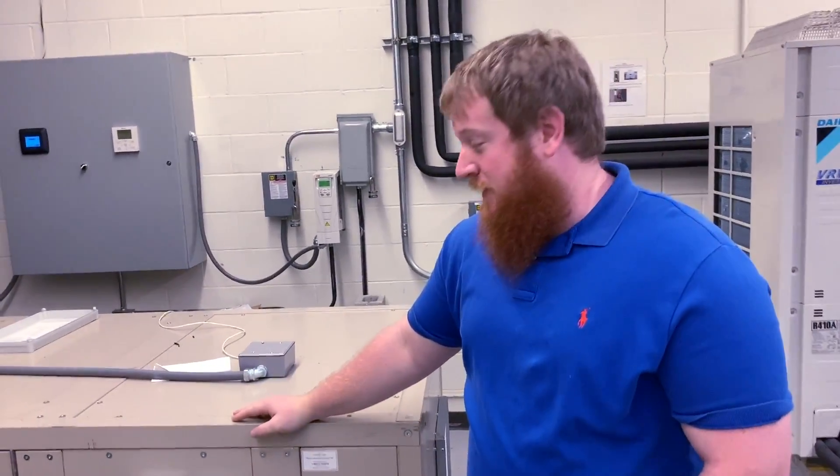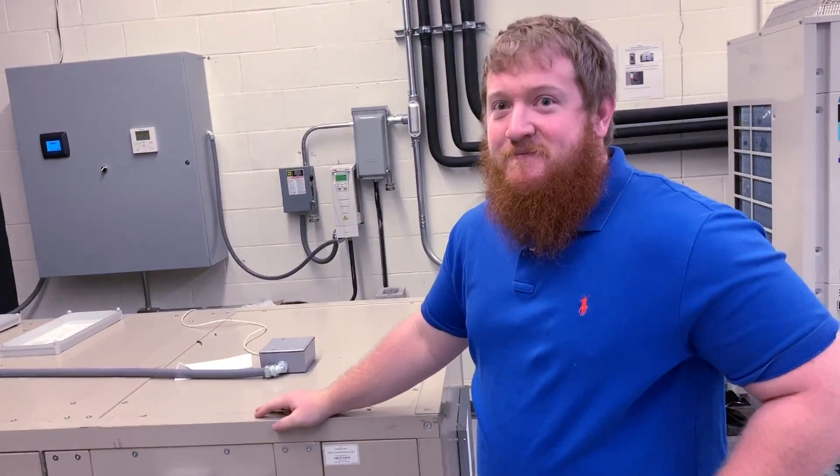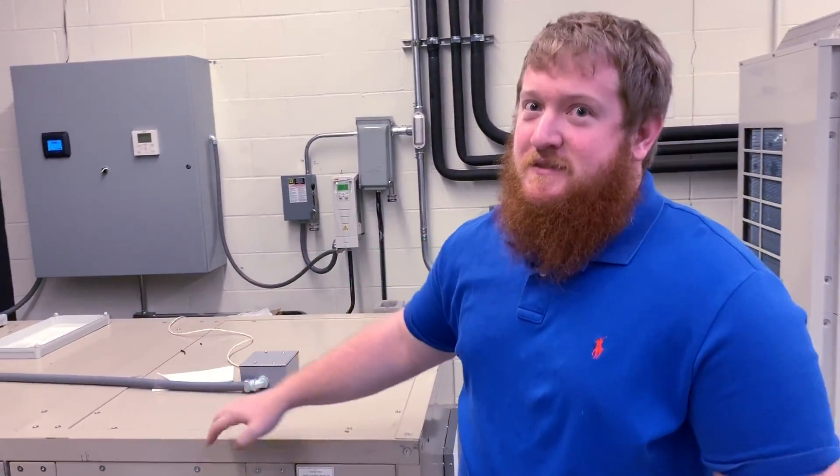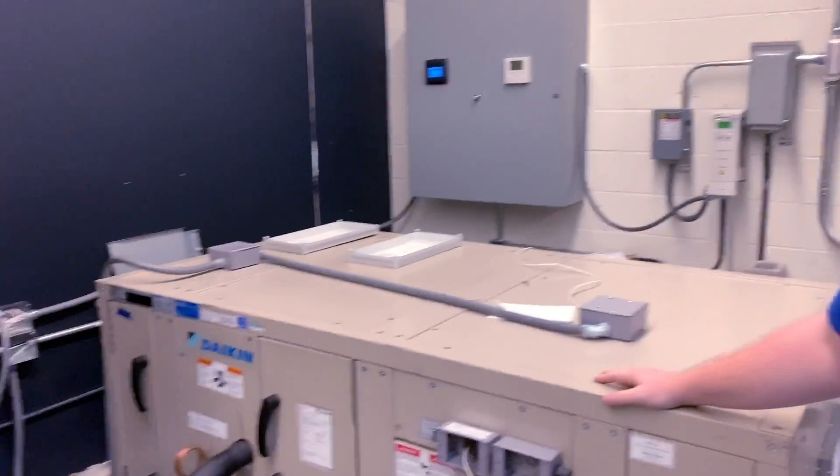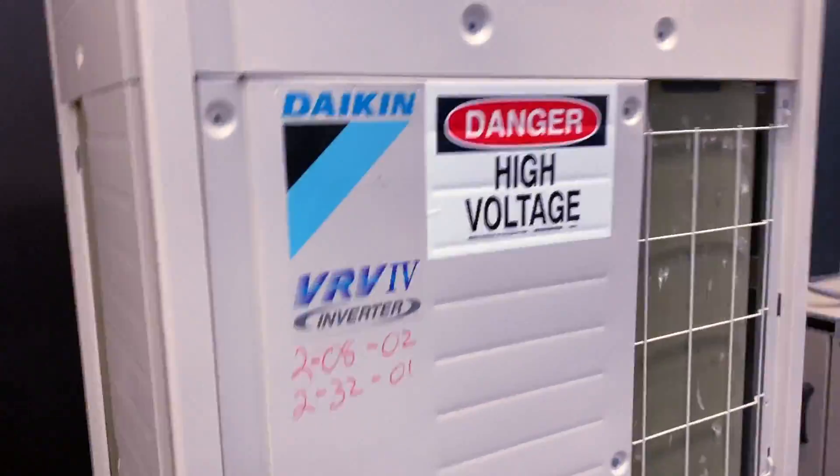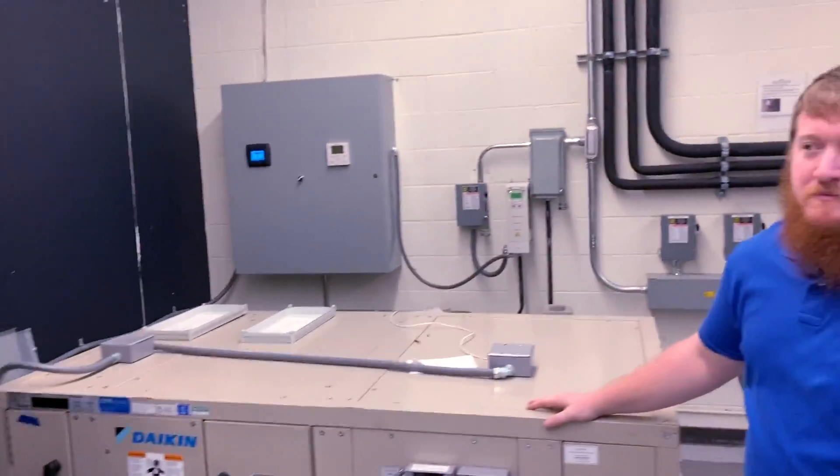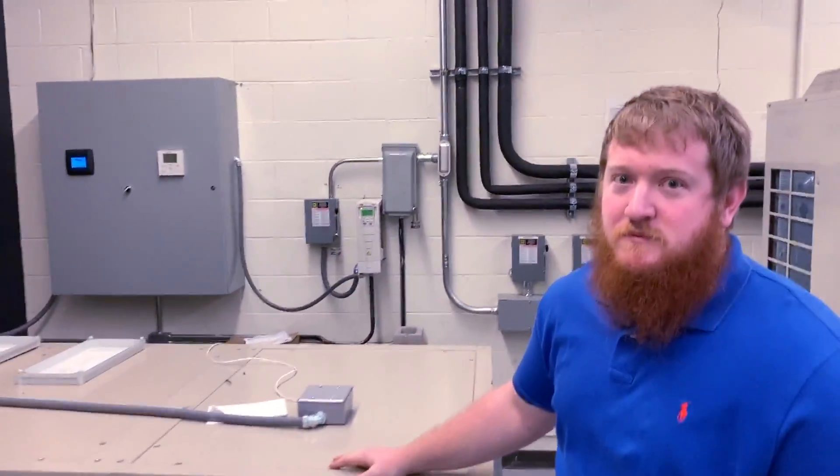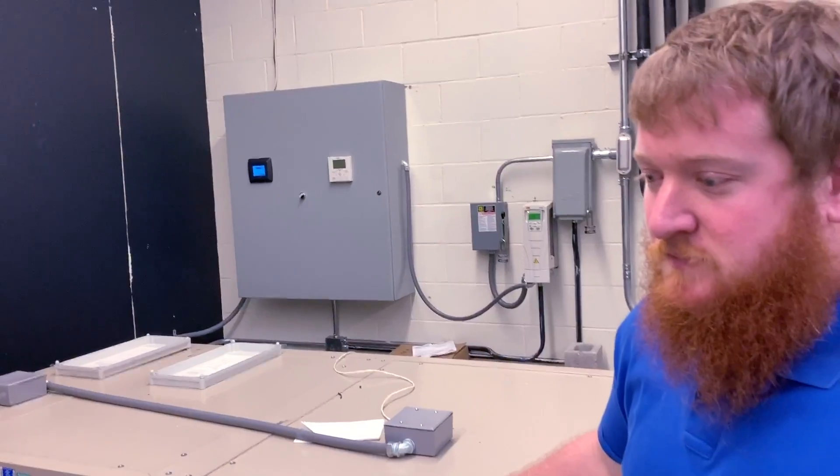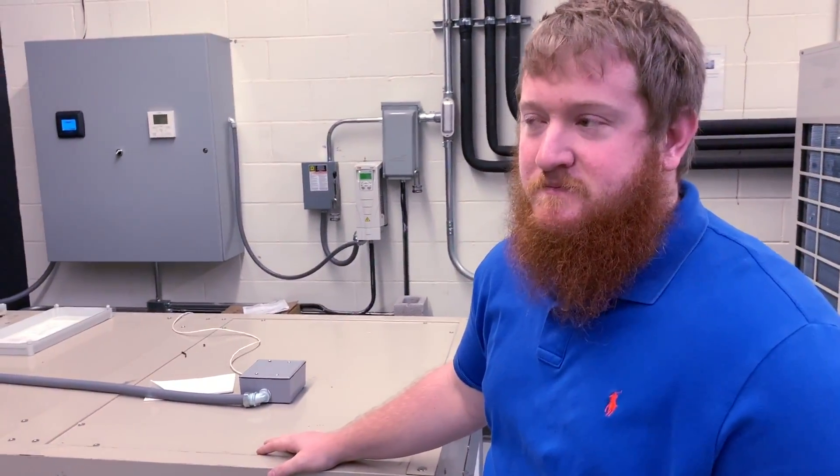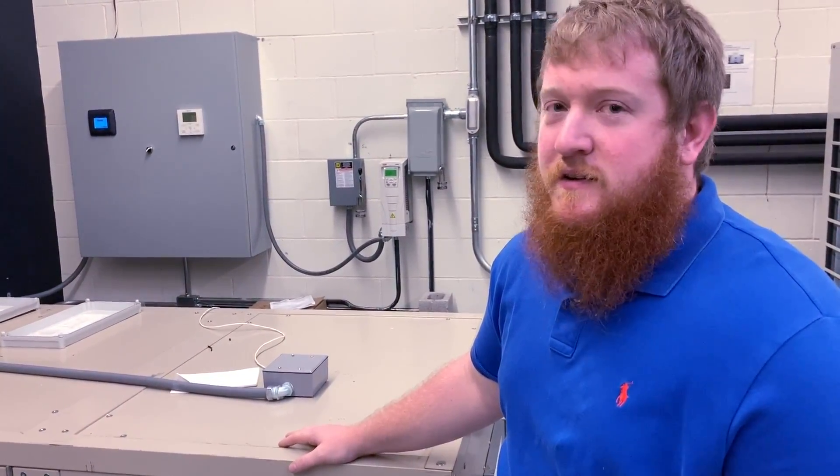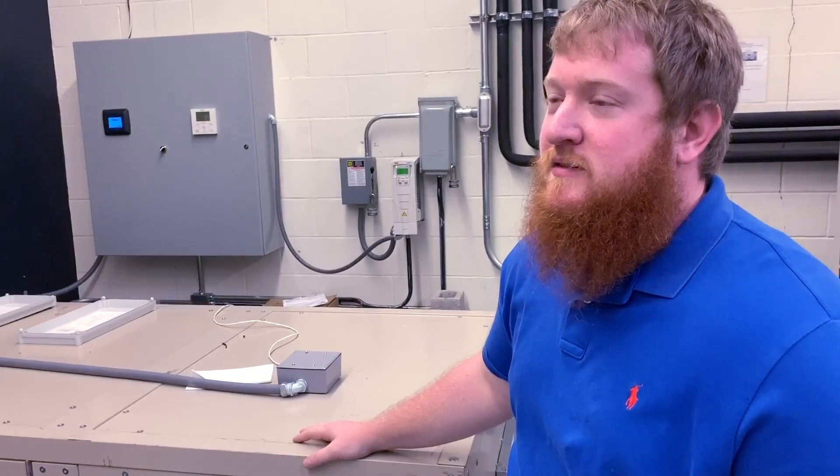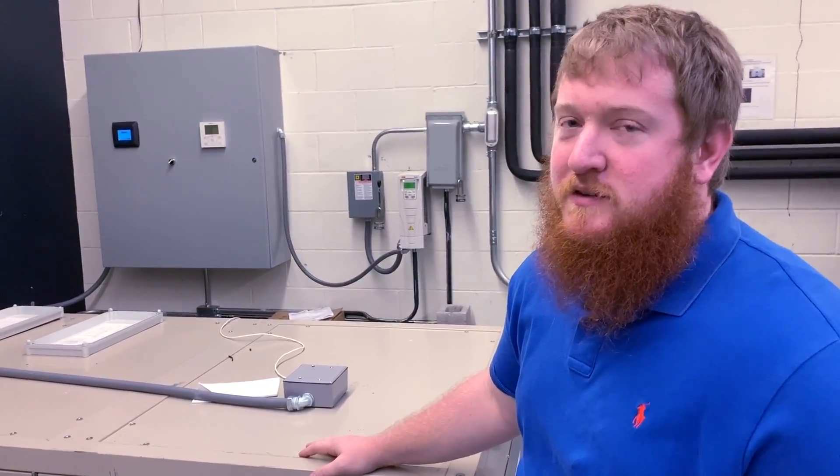In VRV most of the intelligence is going to be in the controls in the condenser. The condenser, that's the brains of the operation. Very cool. Obviously anytime you're dealing with VRV, anytime you have drives and equipment you have to be really careful because you've got pretty high voltages in there if you touch the wrong thing. Very high DC voltage, upwards of 750 volts DC. So it'll kill you, it'll wake you up in the morning.